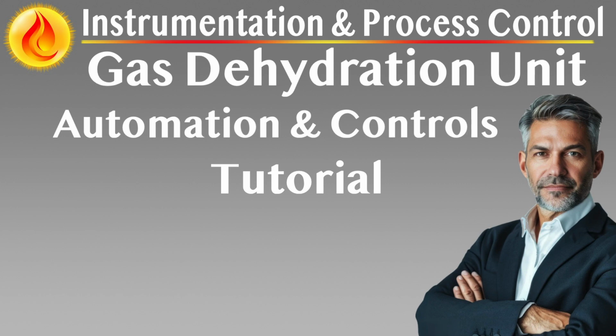Overview. The instrumentation and protective control infrastructure for glycol gas dryers is fundamental to ensuring safe, continuous, and efficient dehydration of natural gas. It facilitates tight regulation of process variables, detection of deviations, emergency protection, and optimization of glycol regeneration and recirculation cycles. All devices and logic systems are specified to conform with process safety integrity levels, SILs, operational reliability expectations, and system-wide integration within control centers or local panels.